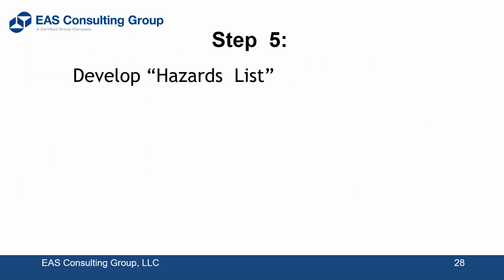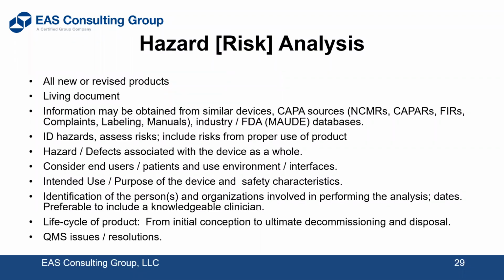Okay, then step number 5 is we develop the hazard list. So here's where we actually get into the main body of the rest of the activity. The hazard list will drive all your other documents. This is a key list of the hazards that your device presents to the field. Now, I'm starting to address some of the complaints that you see sometimes regarding using a failure mode and effect analysis in this by consultants on the internet, is they say it doesn't consider normal use. And there aren't a lot of things that are normal use that cause injury or death, or serious injury or death. But bear in mind that one example I usually use is anaphylactic shock.